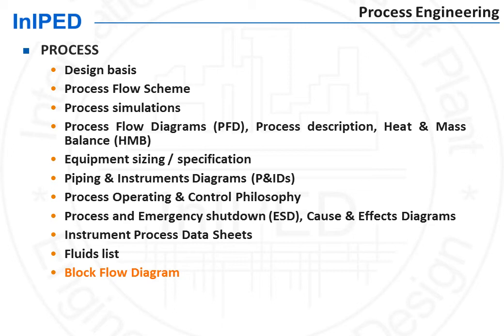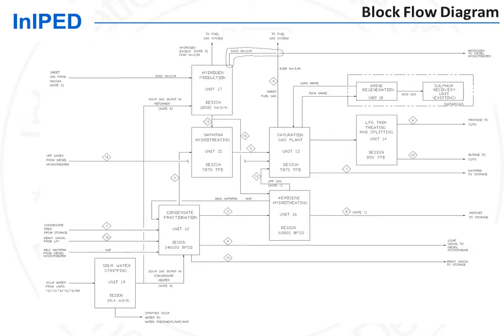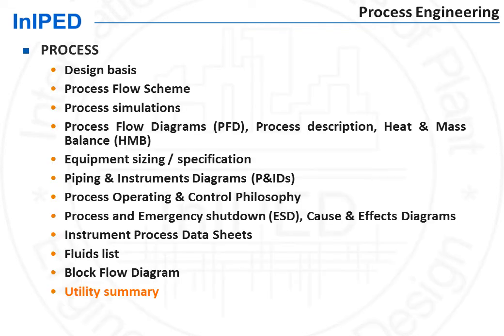A large plant contains several process units. The block flow diagram shows the interconnections between these process units. Process engineering work is usually split by unit. Therefore, the documents we have seen are issued by unit. Once the design of all these process units has been done, process is able to gather the consumption of all of them in the various utility fluids, such as cooling water, steam, fuel gas, and so on. Process consolidates the consumption of the various units in the different plant utilities in the utility summary.